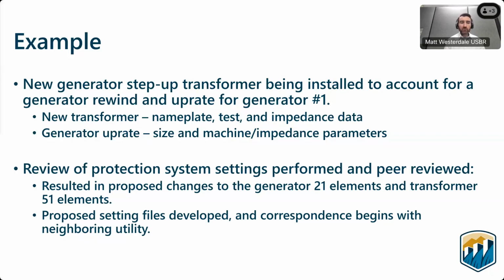Then we move on to the review of the protection system settings. In this example, the protection system settings were reviewed and peer reviewed, and the resulting work indicated that there needed to be changes to our generator 21 elements, the distance elements that look out into the system, as well as our transformer overcurrent 51 elements.